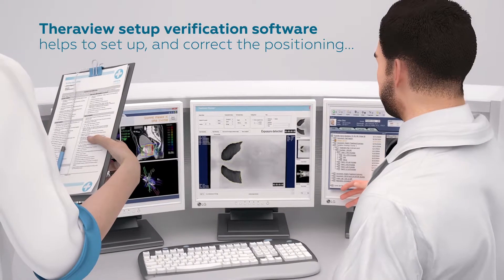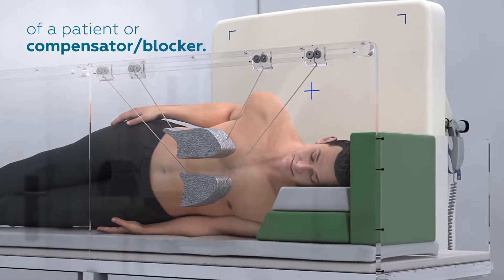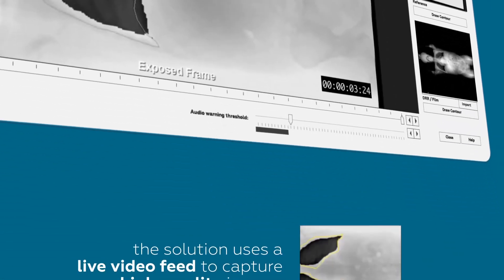Theraview setup verification software helps to set up and correct the positioning of a patient or compensator blocker. Instead of producing a single image, the solution uses a live video feed to capture high-quality images.